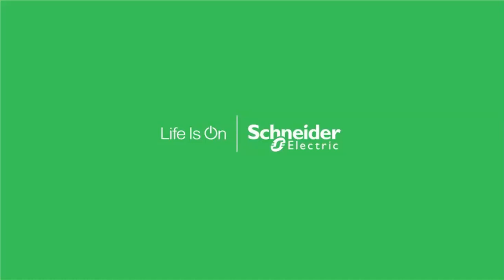Perfect. And I know we're past that hour mark now, but one final question from the audience is, how often should you go back and look at those arc flash studies or reevaluate? Okay. Yeah, good question. NFPA 70E, again, gives us some guidance on that. It has a section that says that arc flash studies should be updated when there are either major changes to the facility or at least every 5 years.